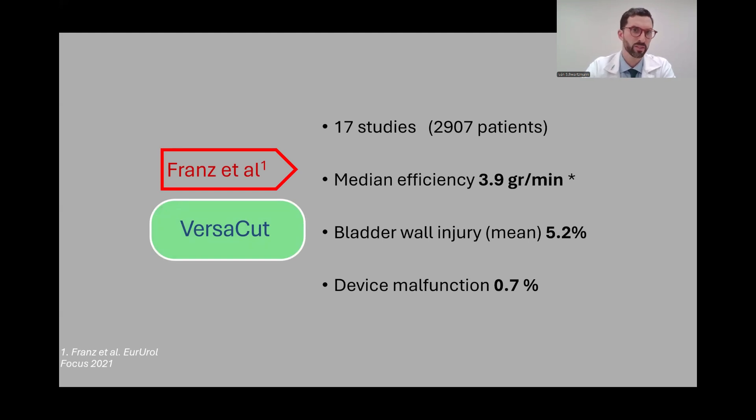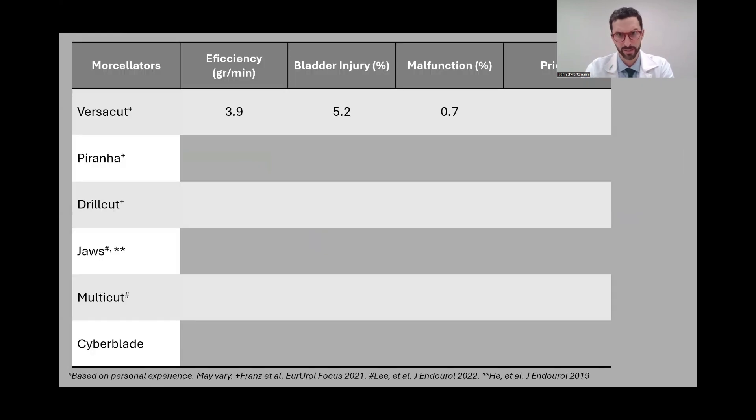A very useful systematic review on morcellators by Franz and colleagues showed 17 studies, almost 3,000 patients on the VersaCut, with a median efficiency of just under 4 grams per minute, a bladder wall injury rate above 5%, and a very low device malfunction rate at less than 1%. This high bladder wall injury rate is probably due to the reciprocating movement of the blades. Regarding price, this is one of the cheapest morcellators available.